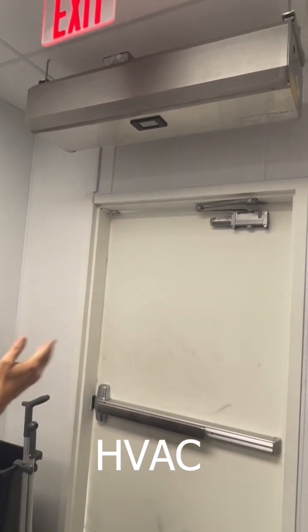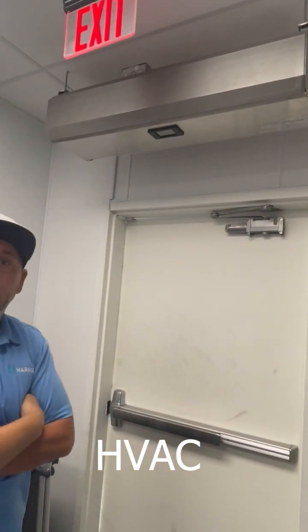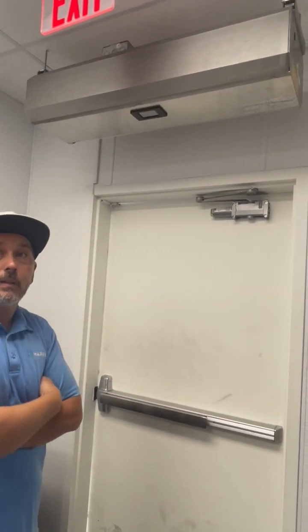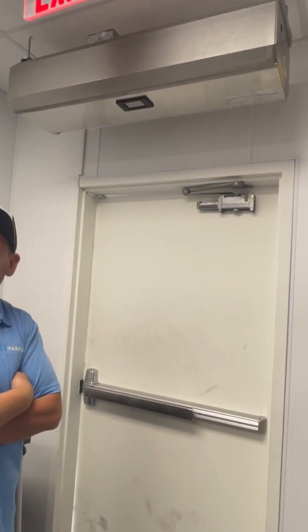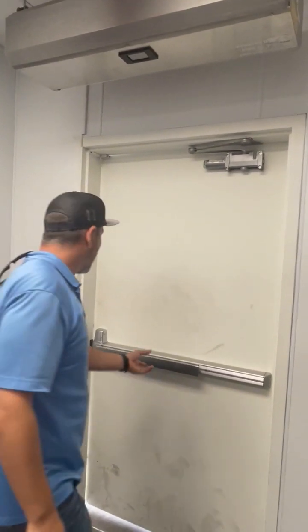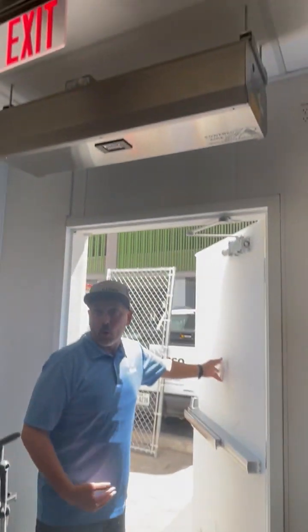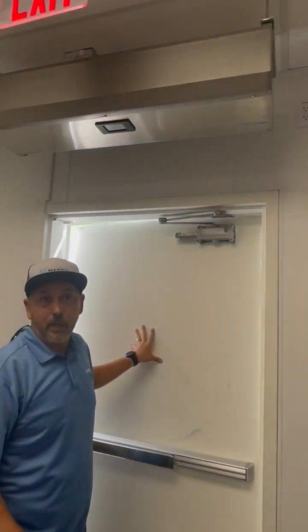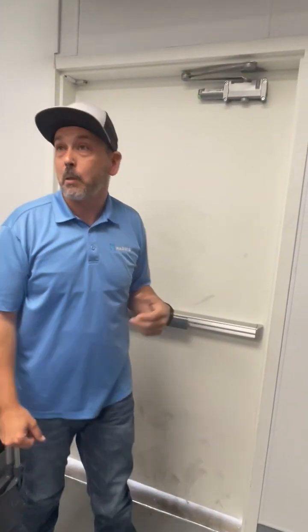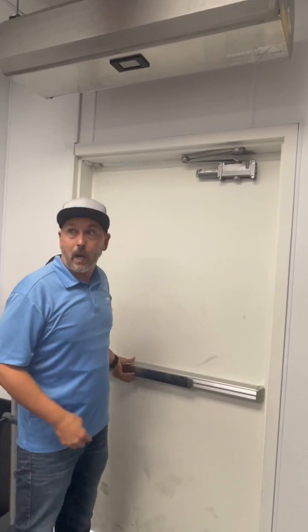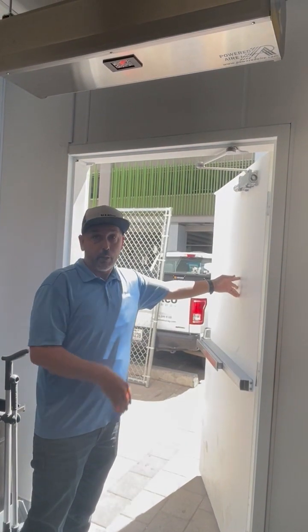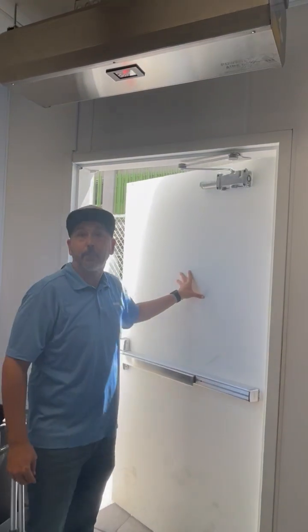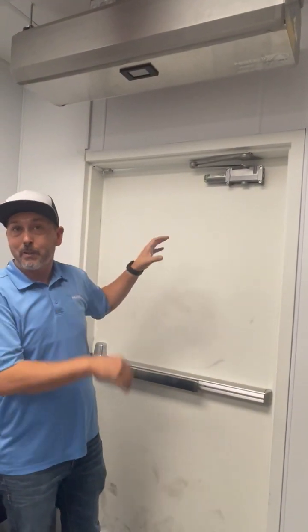These right here are the fly fans, or air curtains, whatever you want to call them. There's really no maintenance to these. There's a washable filter inside that you'd pull off and maintain once every couple months. They work on a door switch - you open the door, the fan turns on. There's no delay on these; some have delays, but as soon as the door switch closes, they shut off. So if this fan doesn't operate when the door opens, there's a door switch or electrical issue. There's no other controls besides this door switch - that's the only thing that turns it on and off.